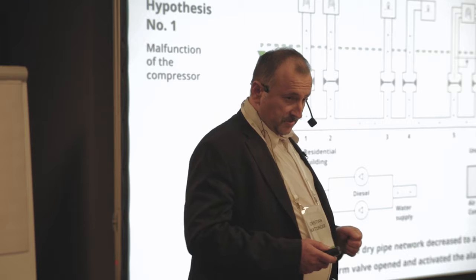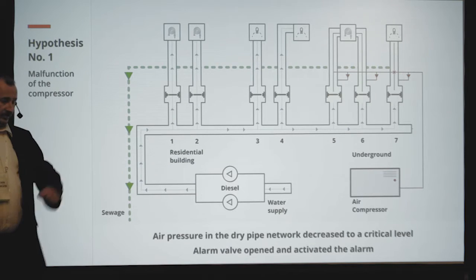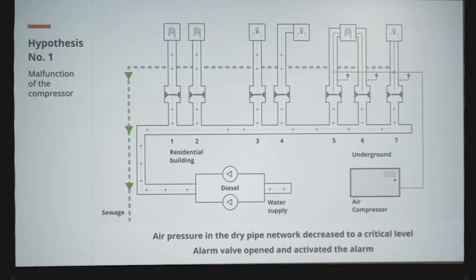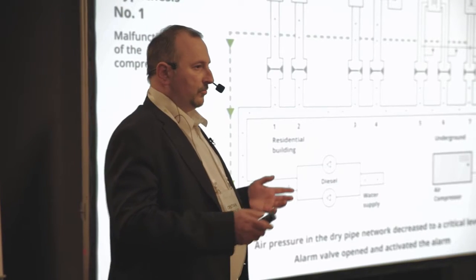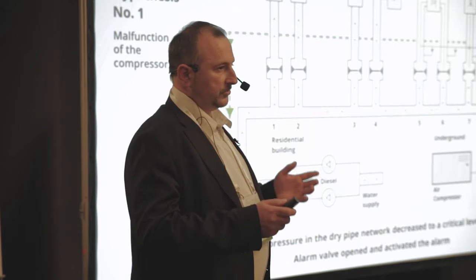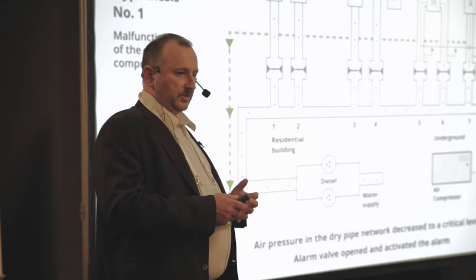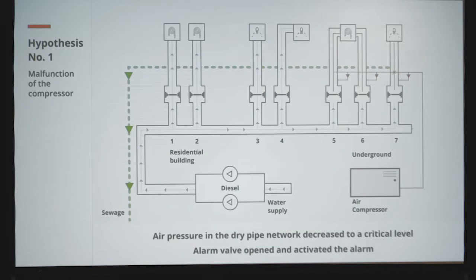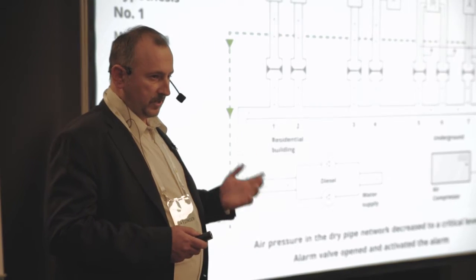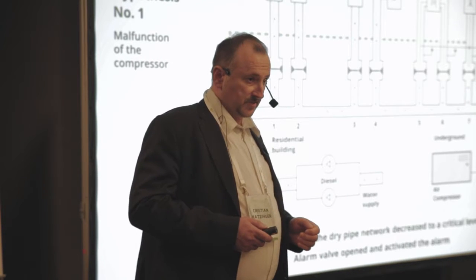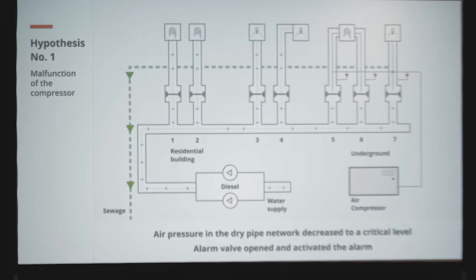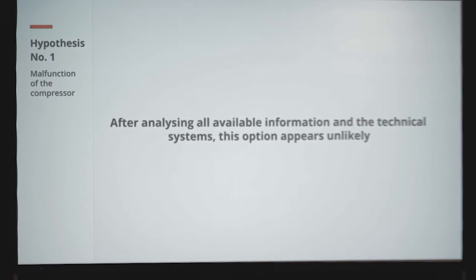But we've got here a ring system, and we have got here an air compressor which is supplying this system. And even if the air compressor would be defective, what happens if there is a small leakage? So the air pressure isn't dropping only in a special area, but is dropping in the whole ring system. So both clappers would have opened, both valves 5 and 6. But in reality, it was only valve 6 which opened. So after analyzing the situation, we came to the conclusion that this option appears unlikely.